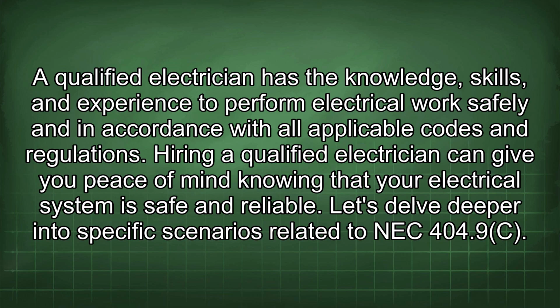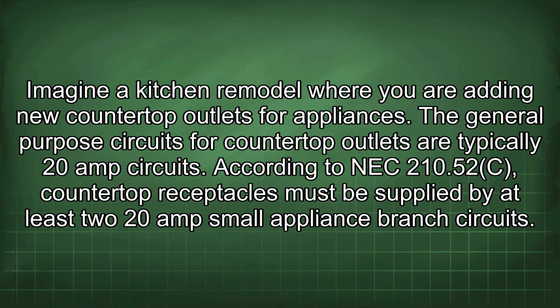Let's delve deeper into specific scenarios related to NEC 404.9C. Imagine a kitchen remodel where you are adding new countertop outlets for appliances. The general purpose circuits for countertop outlets are typically 20 amp circuits. According to NEC 210.52C, countertop receptacles must be supplied by at least two 20 amp small appliance branch circuits.